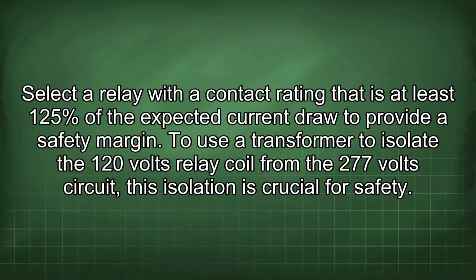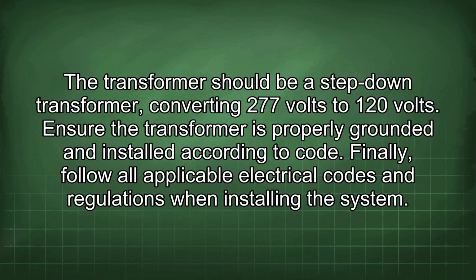Use a transformer to isolate the 120 volts relay coil from the 277 volt circuit. This isolation is crucial for safety. The transformer should be a step-down transformer, converting 277 volts to 120 volts. Ensure the transformer is properly grounded and installed according to code.